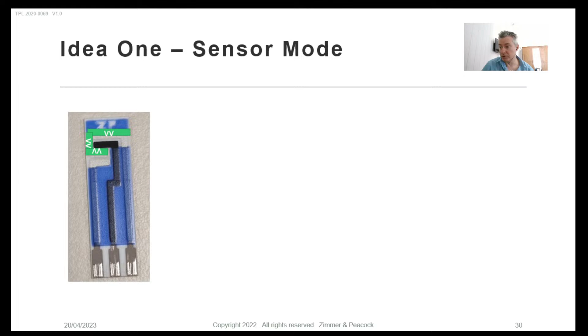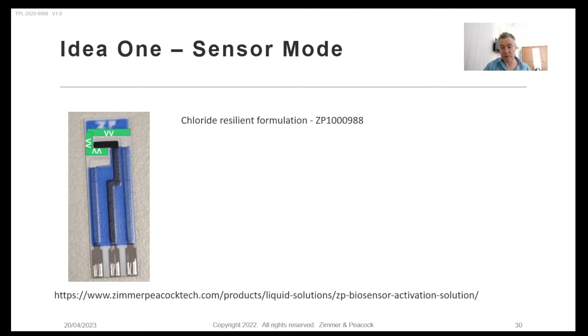I think I'm going to give you 4 ideas. One of them is you take a pipette and you functionalize the reference electrode with something that we call the chloride resilient formulation. The chloride resilient formulation is essentially chloride anions bound up in a polymer. So we're trying to turn what's essentially called a pseudo reference electrode into a true reference electrode by fixing the chloride concentration. So that is a way. I'm slightly reluctant because it takes some effort from you, and it will give you a more stable reference electrode, but eventually the chloride will diffuse out of that reference electrode. So if you're looking for, I'll be extreme, 2 weeks of continuous pH operation, it's not going to work. Unless the sample has a true fixed chloride concentration.